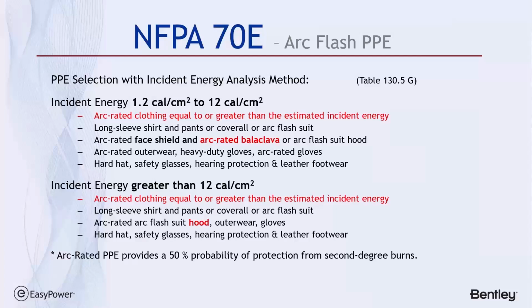The first category, which is less than 12 calories per square centimeter, requires long sleeve shirts and pants, an arc-rated face shield and balaclava or hood, arc-rated outerwear, hard hat, safety glasses, and hearing protection. Greater than 12 calories has the same requirements, but for head protection it requires an arc flash suit hood, as the balaclava is no longer adequate.